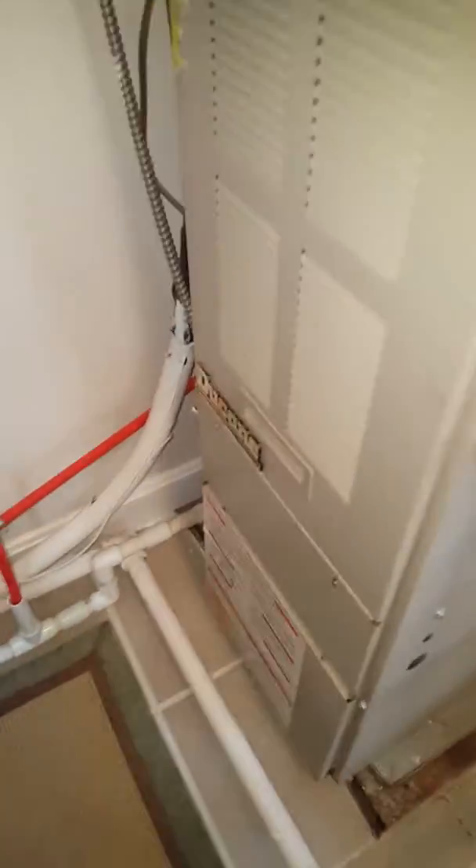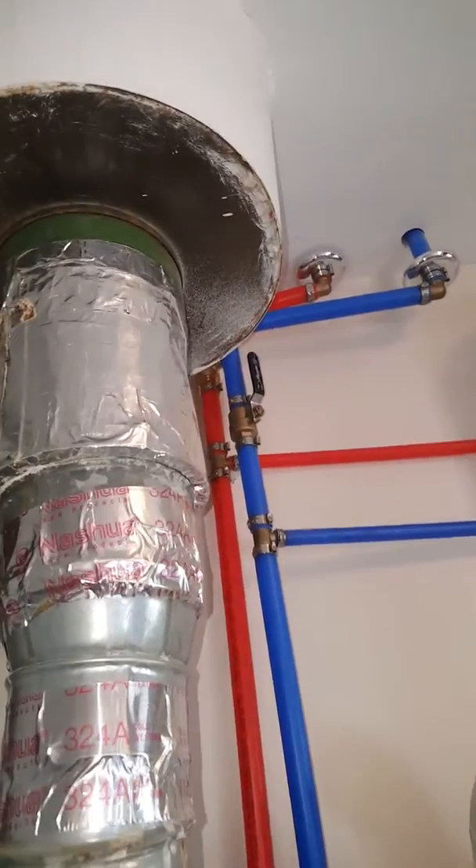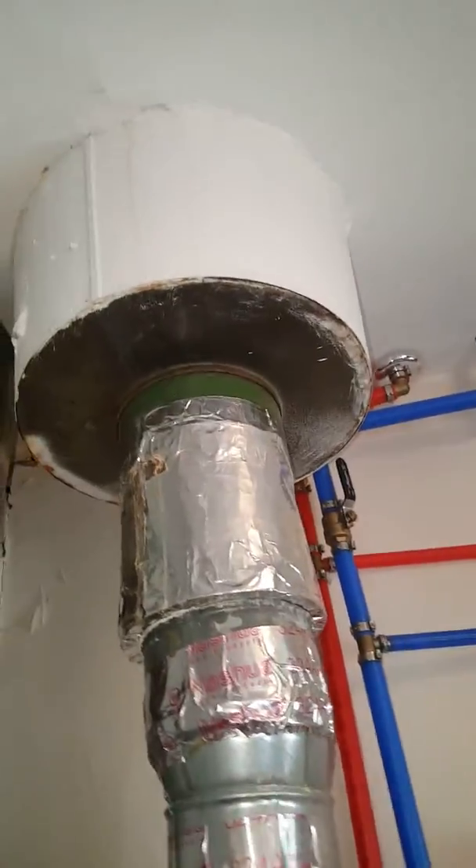This is a video at the Beasley Residence. We have a Ducane 75,000 BTU furnace that has some breaches in the heat exchanger. It's got a three-inch vent that goes into a four-inch vent that goes up through an all-fuel chimney to the roof.